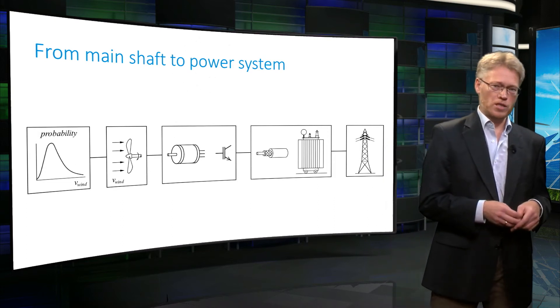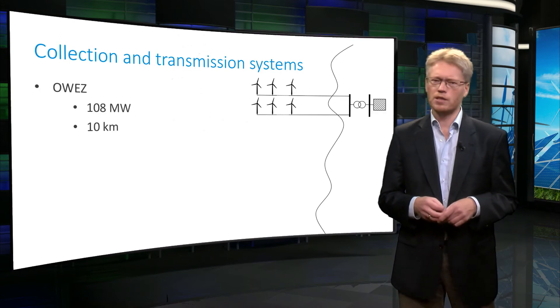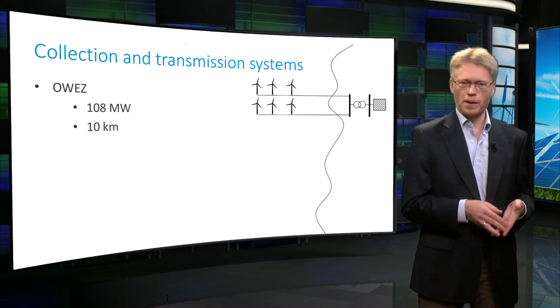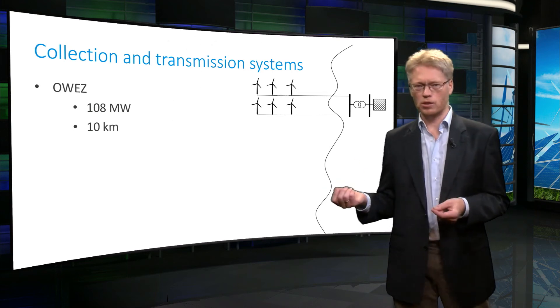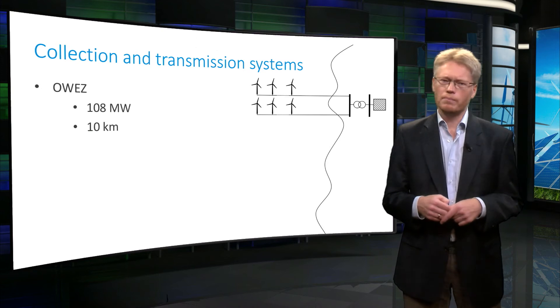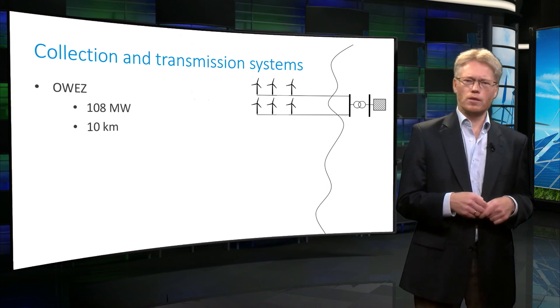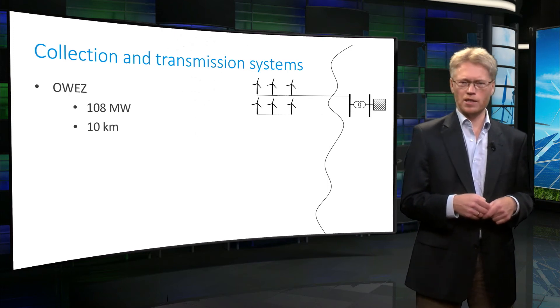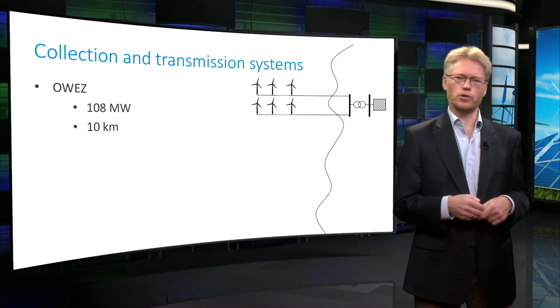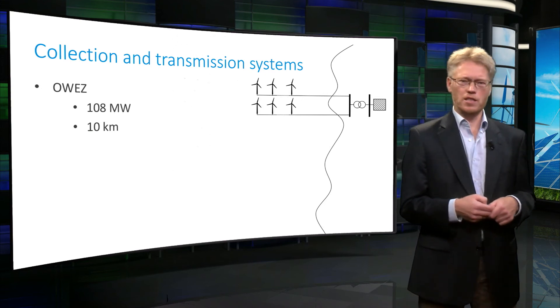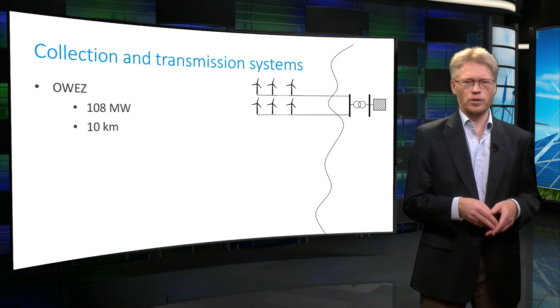For a wind farm, especially offshore, this is more complicated. In a wind farm, a large number of wind turbines are generating electrical power. This power has to be collected within the wind farm, converted to the right voltage level, and transmitted to shore. The way in which this is done mainly depends on the distance to the power system onshore. The offshore wind farm Egmond aan Zee, abbreviated as OWEZ, has a power of 108 MW. At 10 kilometers offshore, it is relatively close to shore. In this case, the power is collected at a voltage level of 33 kV and transmitted to shore at the same voltage level.